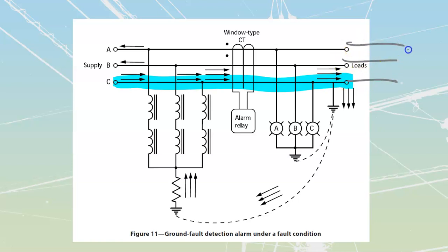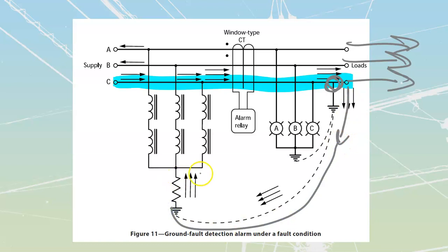Normally - and even with this line faulted, there's still going to be current going out to the load. But there's also now going to be a new current that diverts because this line is grounded right at that point. This new current is going to travel through the bonding system and up through here. We have placed a resistance in here so it's not going to be a dead short with unlimited current, because otherwise we would get a massive runoff of current.